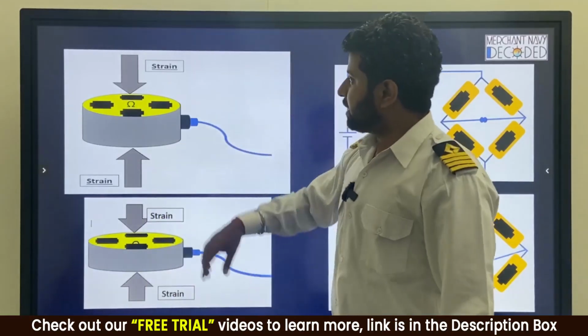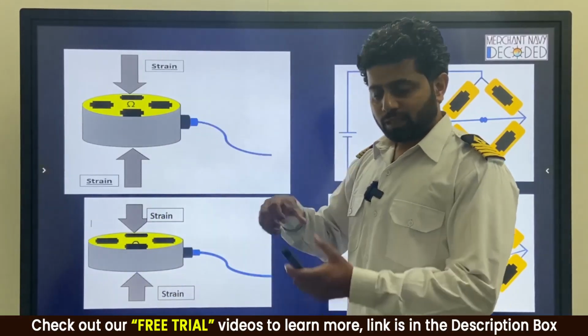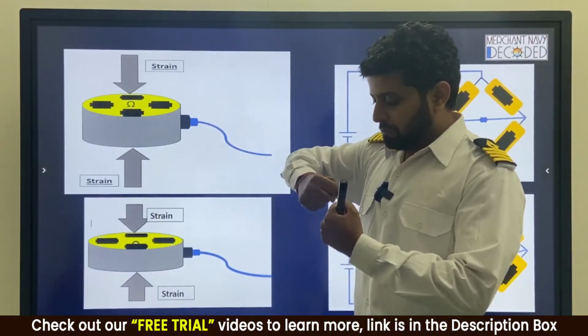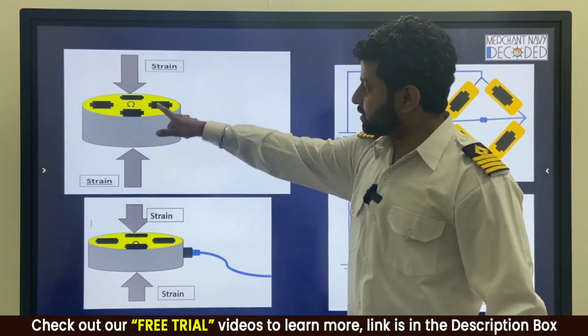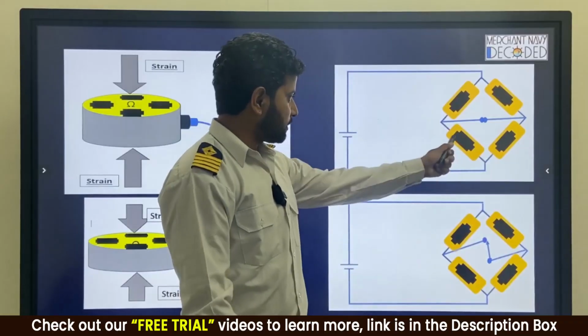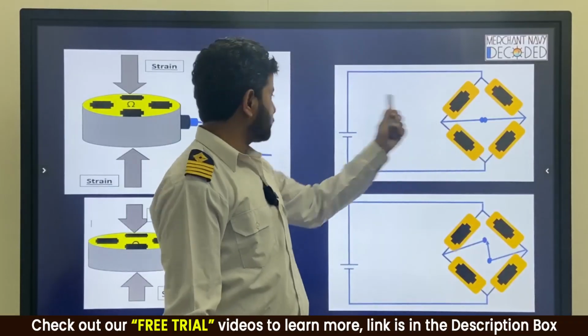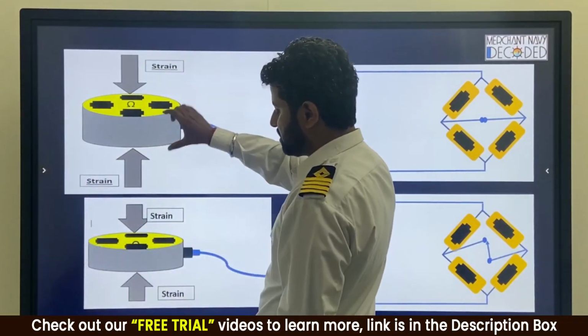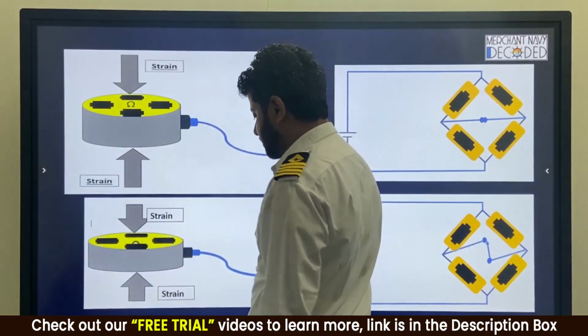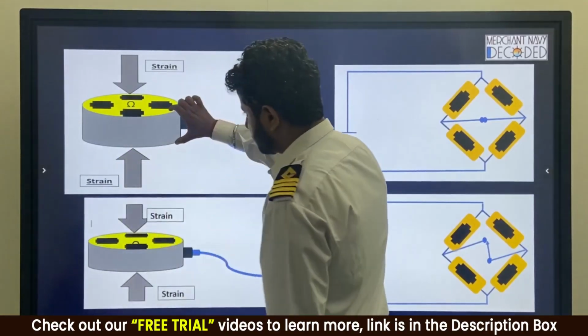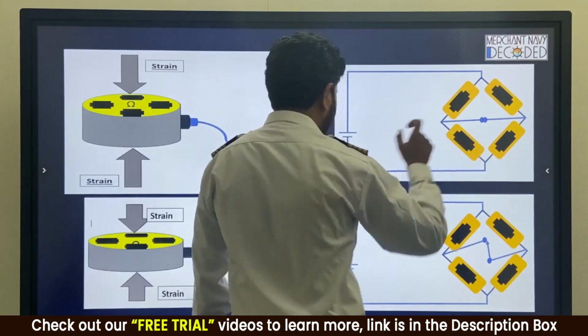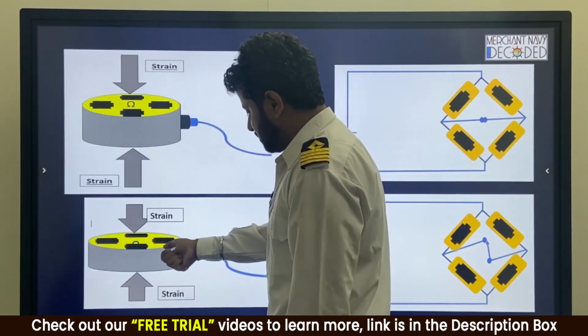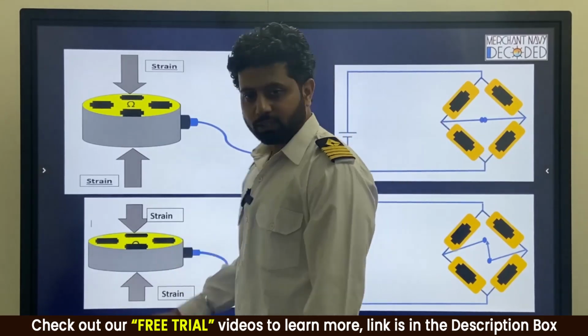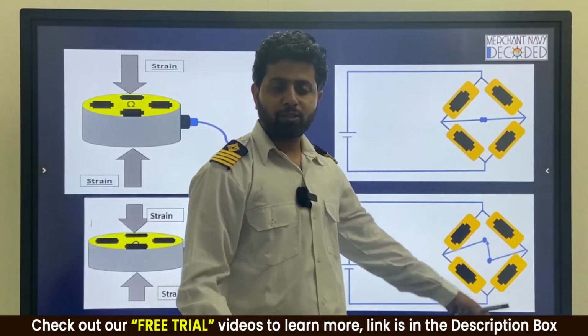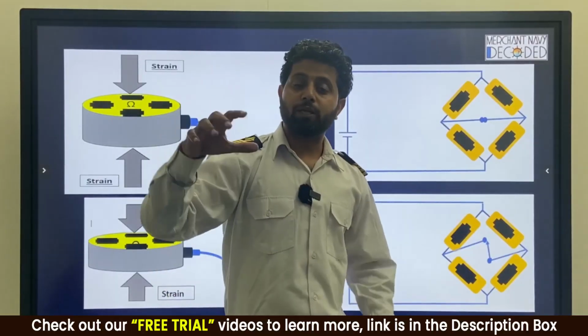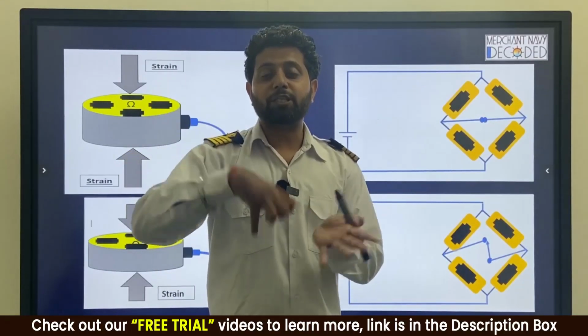So suppose you have put this strain sensor in the pressure transmitter over there. Because of this strain, the length of the resistance has changed. It was normal, a balanced Wheatstone bridge over here, when it was normal like this. But when the length has changed because of the strain over here, earlier it was like this, a balanced Wheatstone bridge. Now when we have put strain, what has happened? Resistance has changed. It has become unbalanced. So measuring this current will also give us a signal, bhaiya kitna pressure hai, how much is the pressure acting.